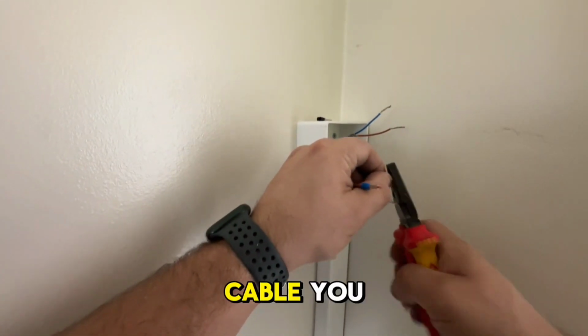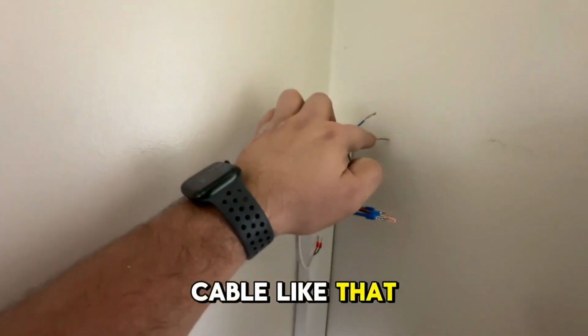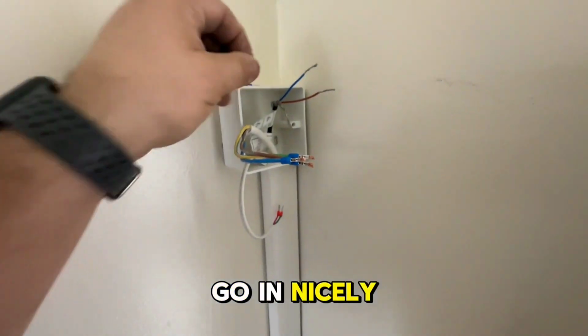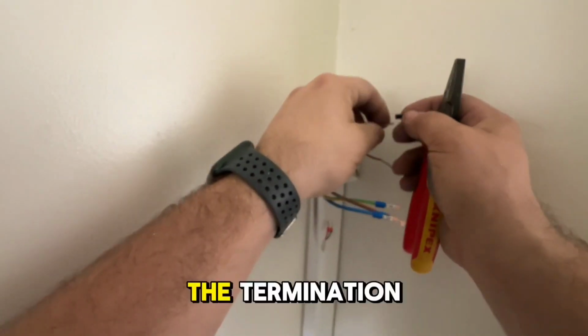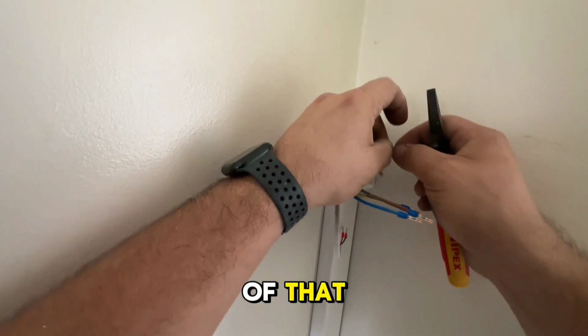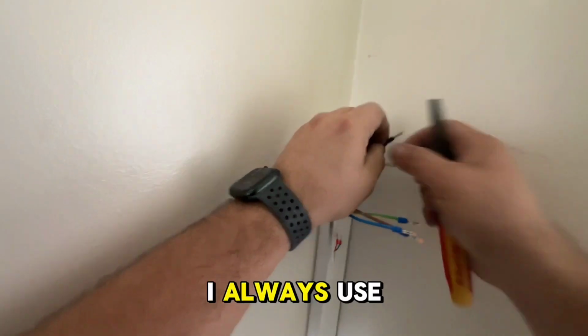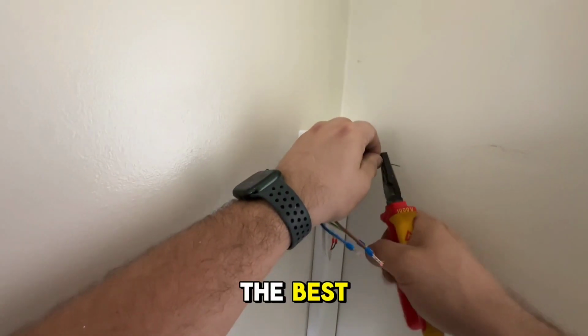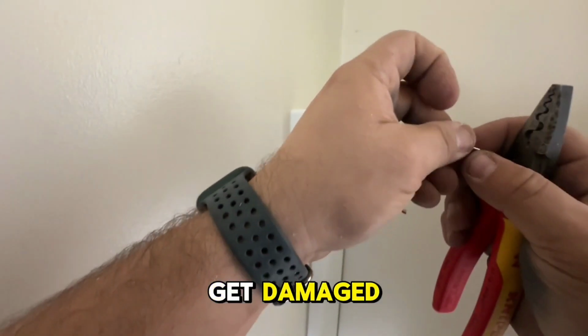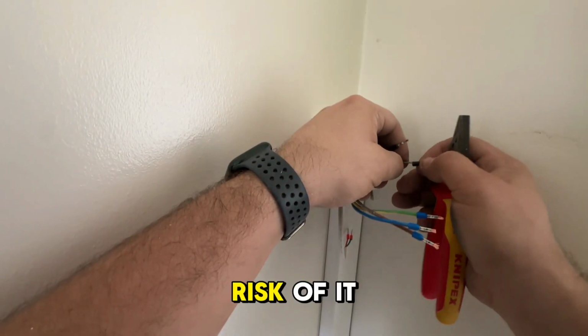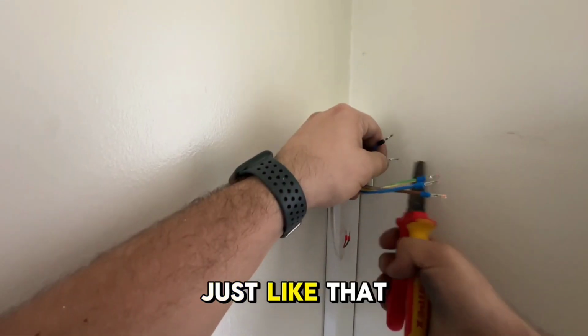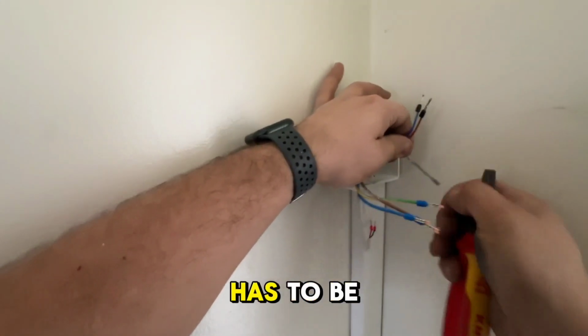With the flex cable, you can just twist cable like that, but that twisted cable is not going to go in nicely into the termination of the back of that thermostat. So I always use crimps. They are the best, and that cable is not going to get damaged as well. There's no risk of it popping out. Just like that. For that earth sleeving, it has to be earthed.